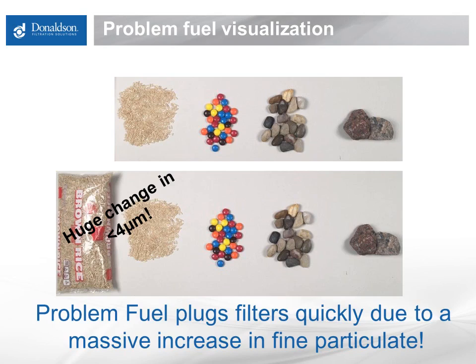Diesel fuel must be liquid to filter out the damaging hard particles. Next, biodiesel blends generate large amounts of solids as the fuel cools or absorbs water. A certain trace component in the bioblend, called glycerin, begins to form solids at temperatures as high as 55 degrees Fahrenheit. The presence of water in or with the fuel will cause even greater solids formation. These solids come out of solution as sub-4 micron particles and can agglomerate into larger particles over time, plugging filters.